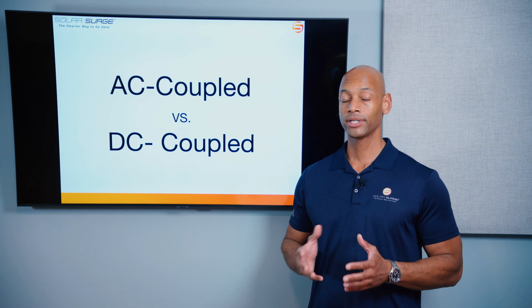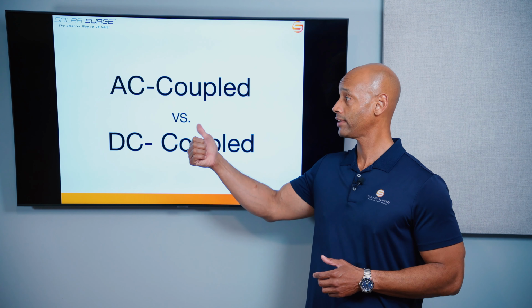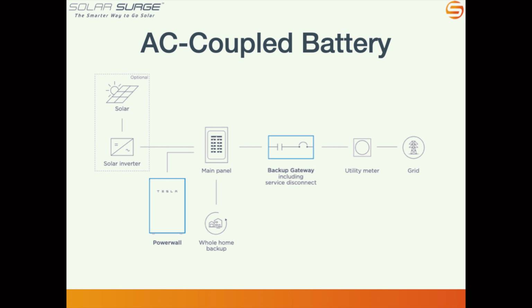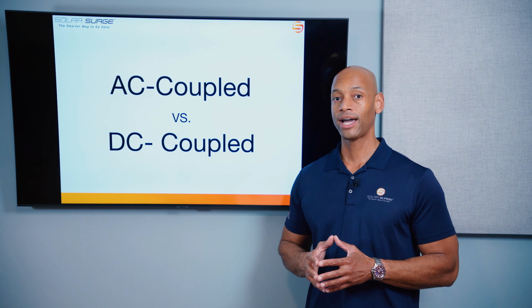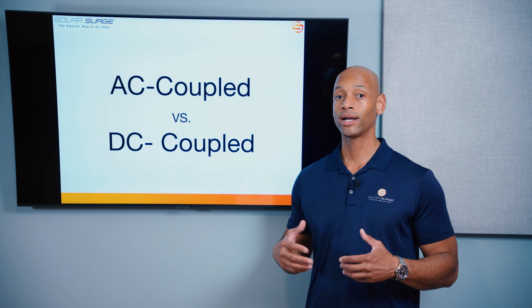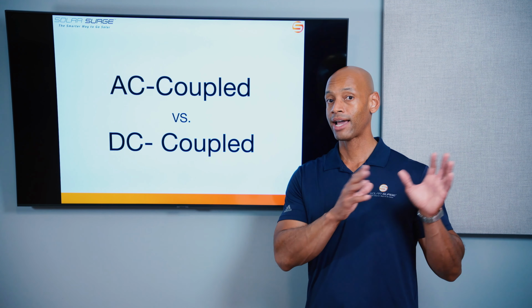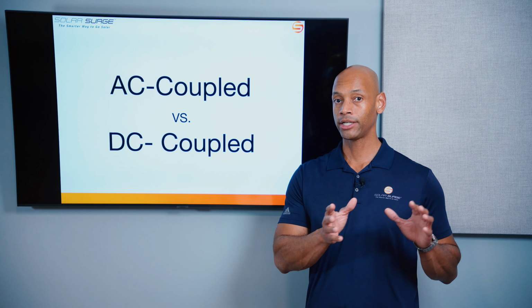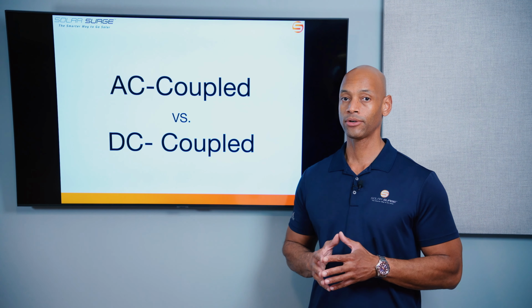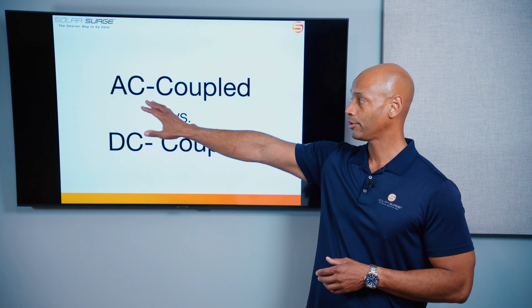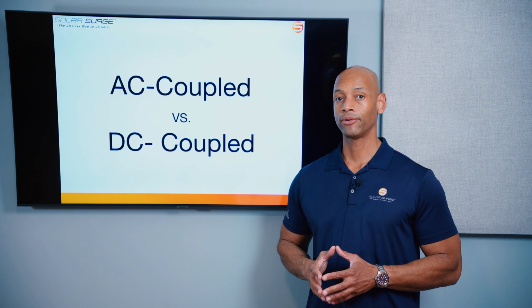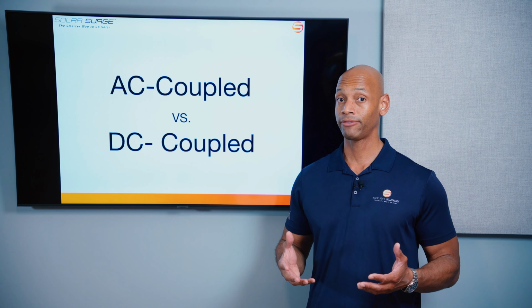There's a couple of pros and cons of each approach. The advantage of an AC coupled battery is that all that connection can be done at ground level at the AC circuit breaker panel. So if you have an existing solar power system and you want to add batteries to it without having to change anything on the roof or potentially void the warranty on your existing solar system, an AC coupled battery allows you to do that more easily. However, you're going to sacrifice efficiency.